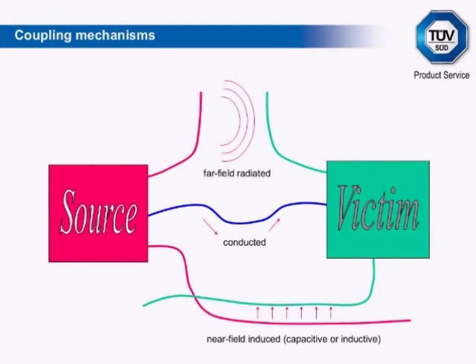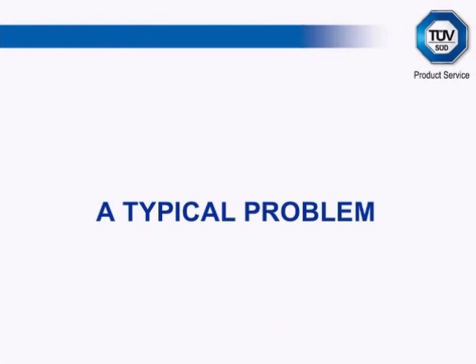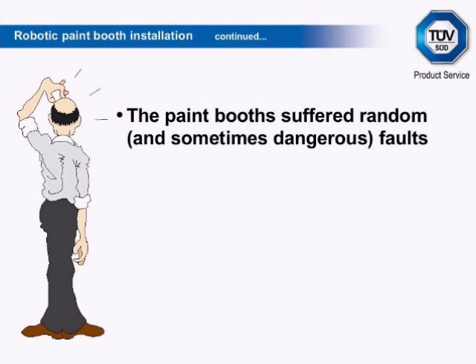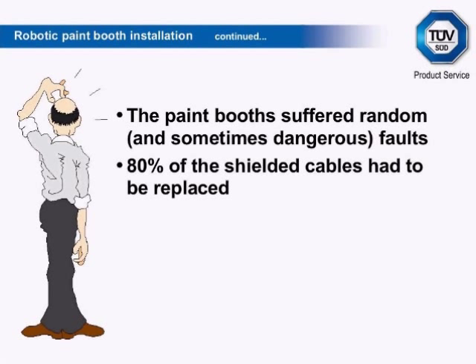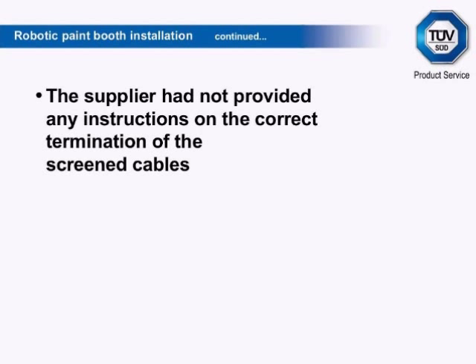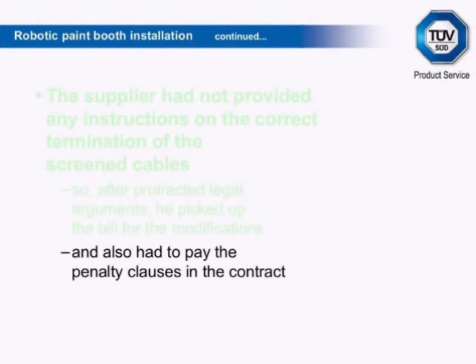As a typical EMC problem from a commercial aspect: a major manufacturer of automotive parts commissioned a series of robotic paint booths. To save cost, it was agreed that the cabling would be installed by contractors. This large equipment involved both movement and solvent spray — from a safety point of view, we don't want the robot moving or spraying solvent when it shouldn't be. The paint booths suffered random and sometimes dangerous faults. After an EMC investigation, 80% of the shielded cables had to be replaced using correct shield termination. The supplier had not provided any instructions on correct termination of the screened cables, so after protracted legal arguments, he picked up the bill for the modifications and also had to pay the penalty clauses in the contract.